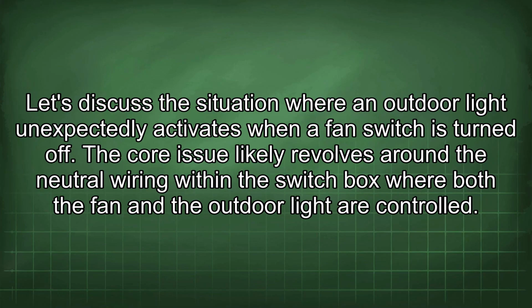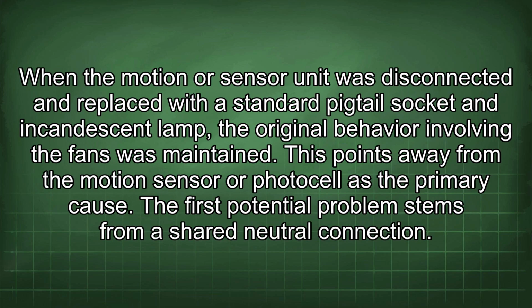Let's discuss the situation where an outdoor light unexpectedly activates when a fan switch is turned off. The core issue likely revolves around the neutral wiring within the switch box where both the fan and the outdoor light are controlled. When the motion or sensor unit was disconnected and replaced with the standard pigtail socket and incandescent lamp, the original behavior involving the fans was maintained. This points away from the motion sensor or photocell as the primary cause.